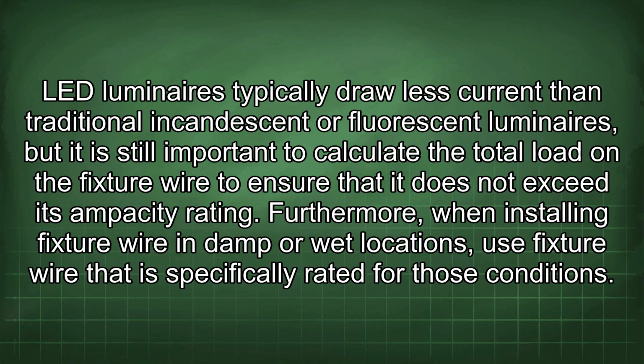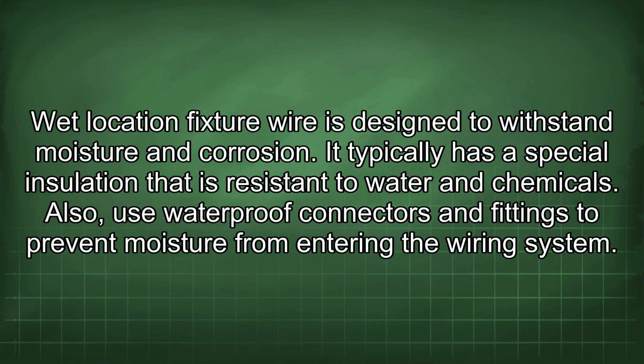Furthermore, when installing fixture wire in damp or wet locations, use fixture wire that is specifically rated for those conditions. Wet location fixture wire is designed to withstand moisture and corrosion. It typically has a special insulation that is resistant to water and chemicals. Also, use waterproof connectors and fittings to prevent moisture from entering the wiring system.